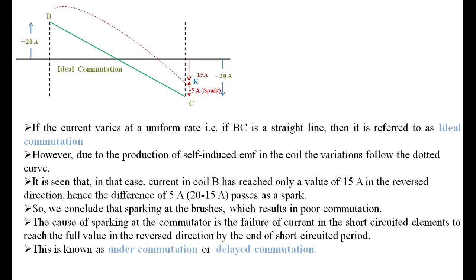Therefore, if there is a change in the current from one direction to the other, because of this self-induced EMF, the coil variation follows the dotted curve. It is not fully changing from plus 20 amperes to minus 20 amperes. It is seen that the current in coil B has reached only minus 15 amperes in the reverse direction. Hence the difference of 5 amperes - that is 20 minus 15 - passes as a spark. We conclude that sparking at the brushes results in poor commutation. The cause of sparking at the commutator is the failure of the current in the short-circuit element to reach its full value in the reverse direction by the end of the short circuit period.